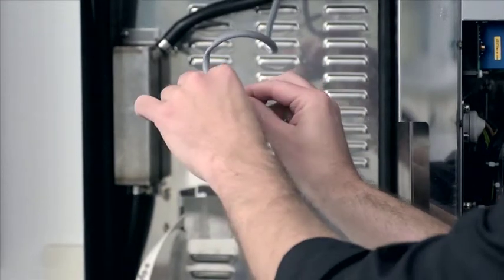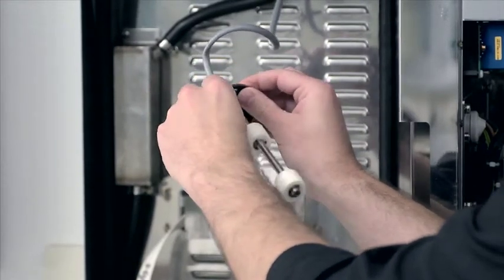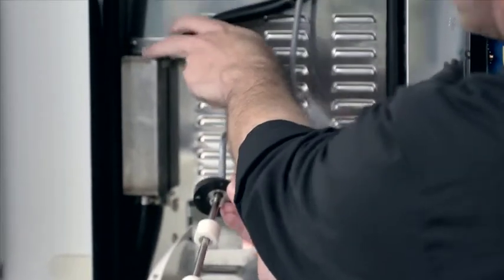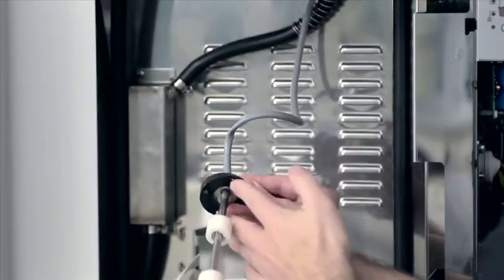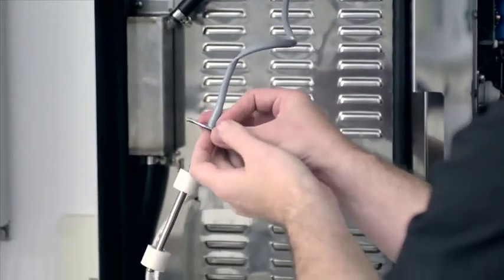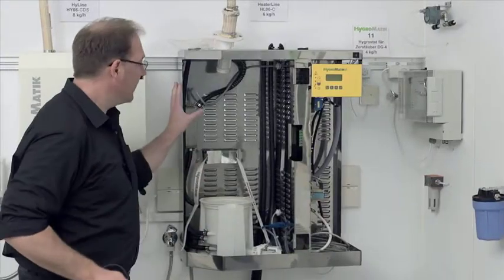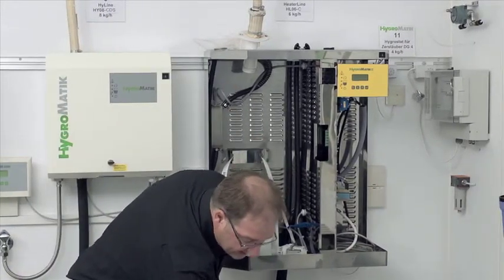I can very well use the flat seal again because it will definitely seal tight. I just have to make sure that there is no coarse residue on top here. Otherwise it will be hard to get it to seal right. After we have cleaned everything, I reassemble the cylinder. To do this I must however still replace the O-rings.